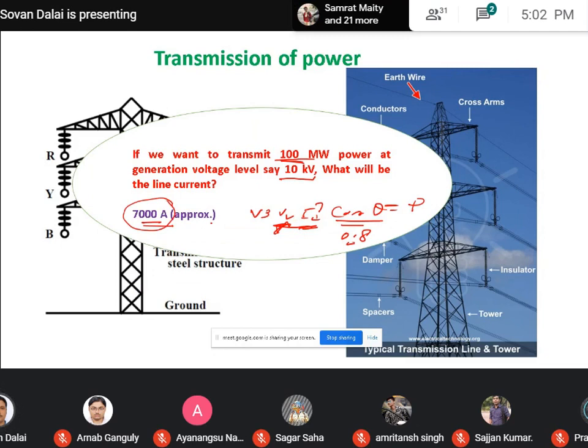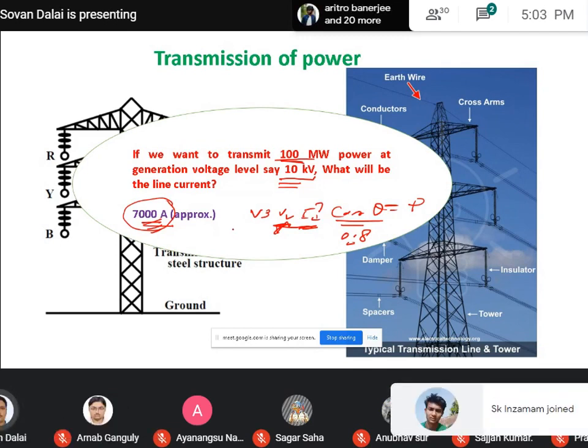Mind that. We have to transmit the power through a transmission line. That line conductor should be capable of carrying a current in the range of 7,000 ampere if we transmit the power at 10 kilovolt. Mind that this current rating is huge. So what is the size of the transmission line conductor? That should be huge, because as all of you know, if the current level increases, the cross section of the conductor increases.